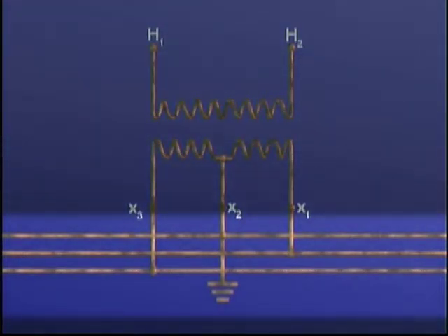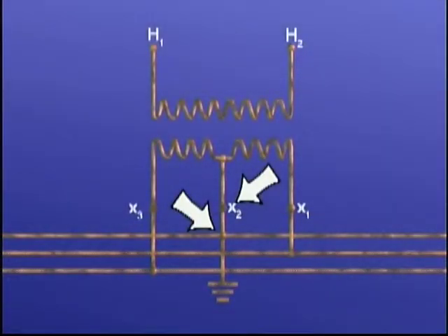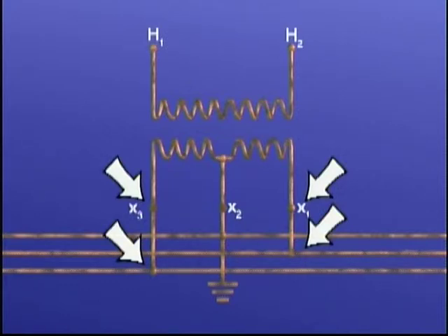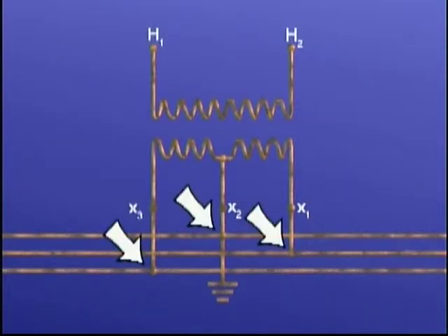One wire, usually referred to as the neutral, is connected to ground and the X2 bushing. The remaining wires, generally called hot legs, are connected through leads to the X1 and the X3 bushings. Connections between the grounded neutral and either one of the hot legs will supply 120 volts. Connections between the two hot legs will supply 240 volts.